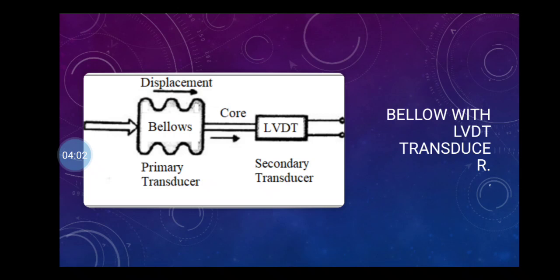The figure shows the input of the bellow is a pressure, the output of the bellow is a displacement, while this is the input of the LVDT. That means the input of the LVDT is displacement and the output is the voltage. The bellow arrangement is a primary transducer, and due to the applied pressure the magnetic core moves in the hollow bobbin.